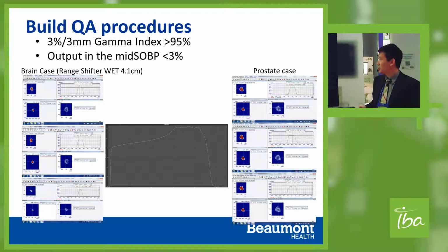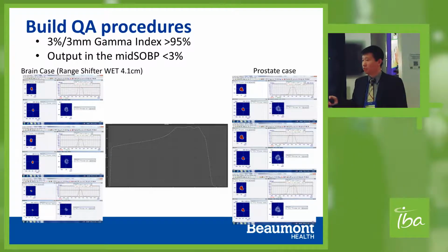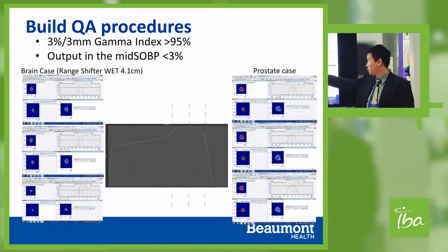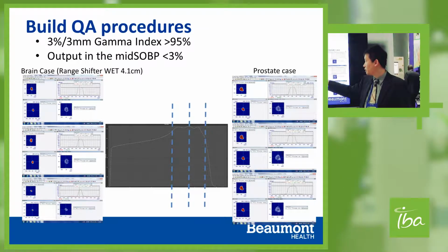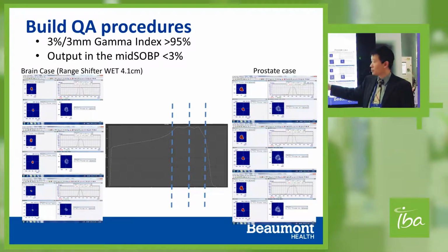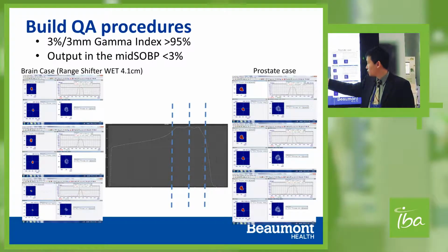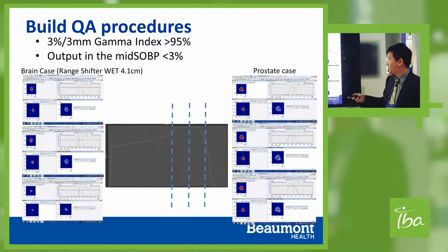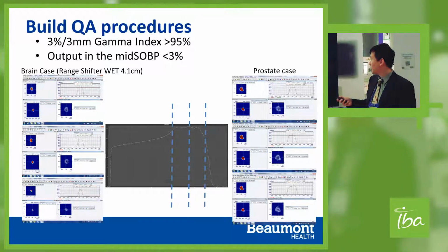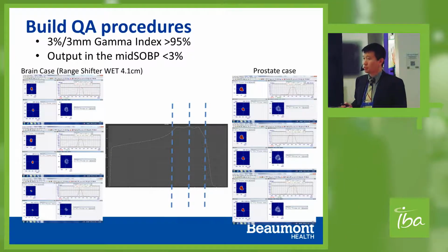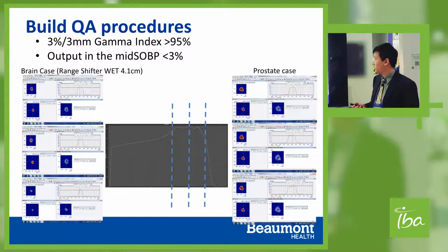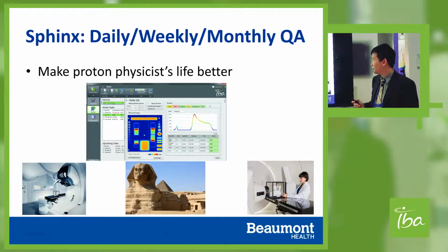So for the patient QA, pretty much everybody uses the same standard. We measure 3 layers. For distal end, you check the energy accuracy. Middle point checks your output accuracy, and also for the proximal, you check your fluence. So this is a different case from the brain and prostate. So our criteria is 95% passing criteria for the 3% 3 mm. The output smaller than 3% is our criteria.